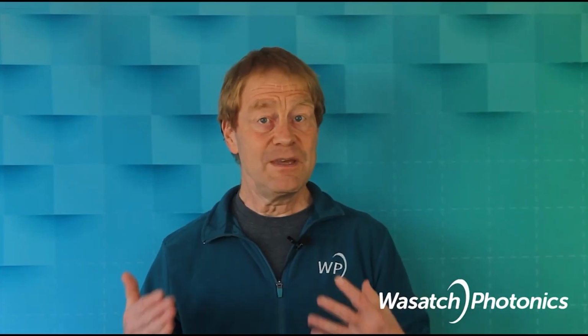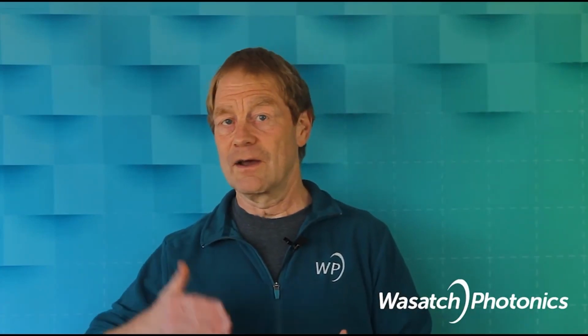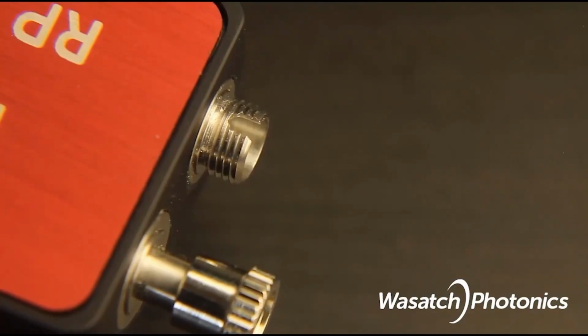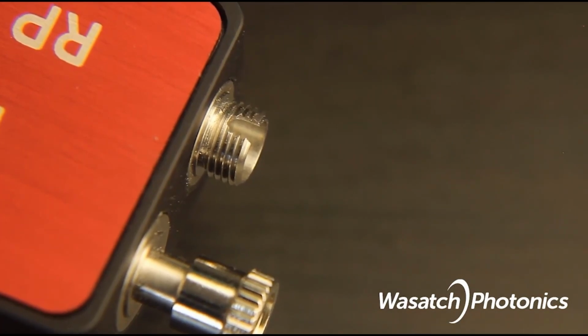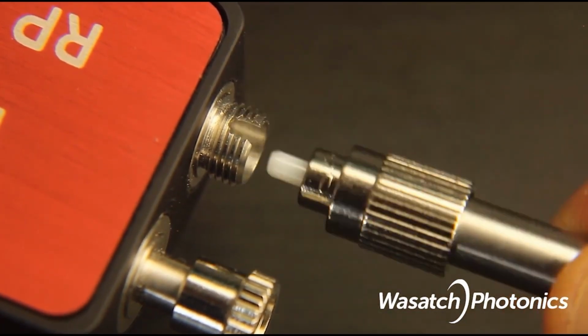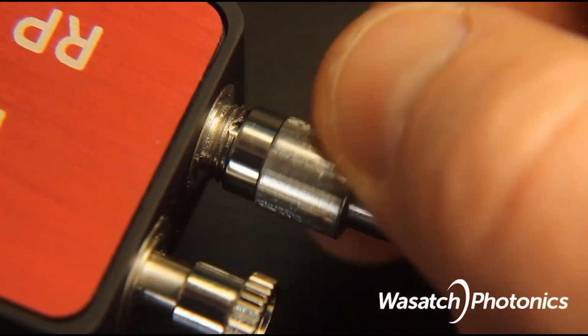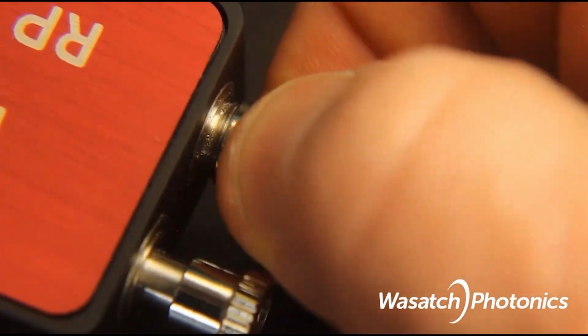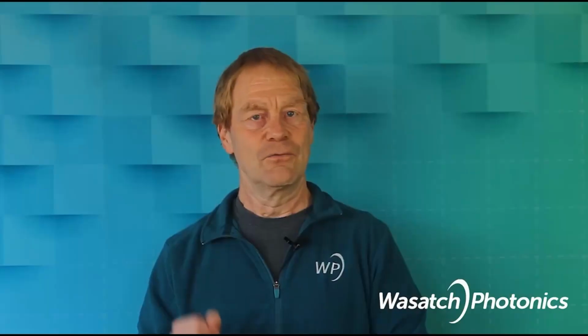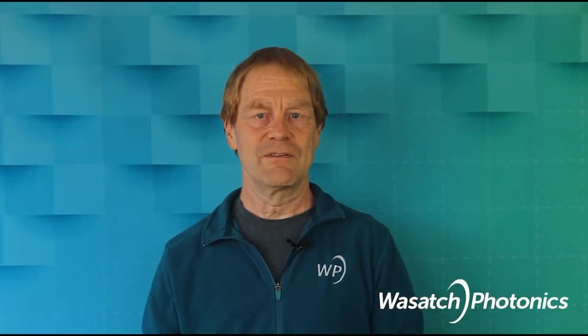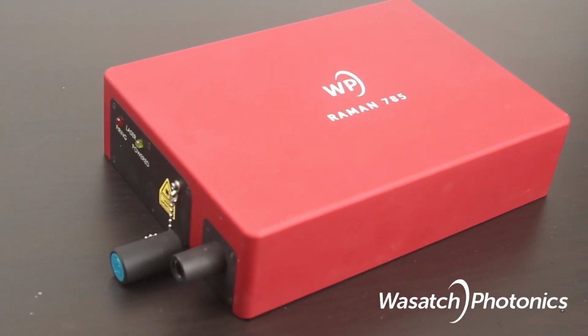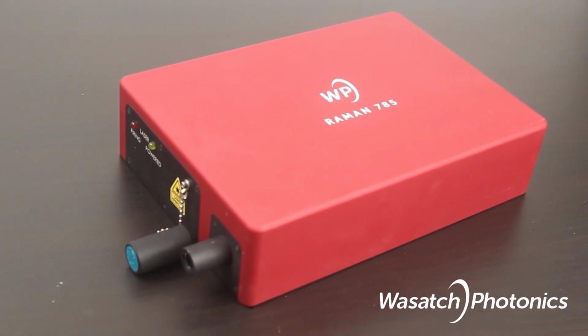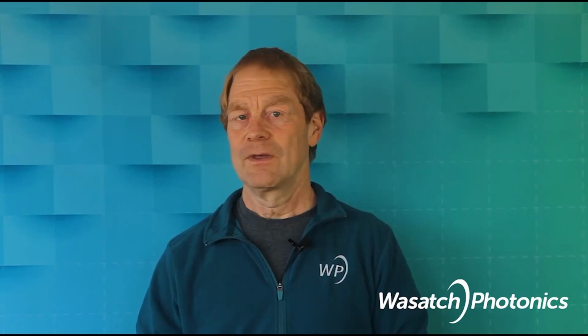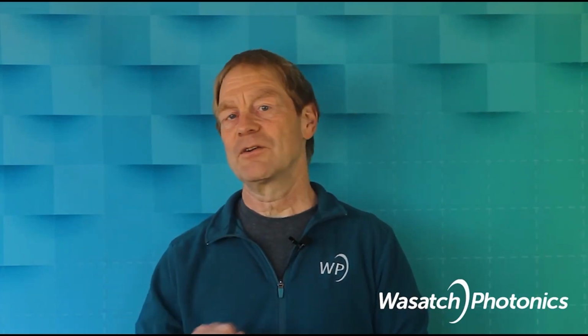The same FC-PC connection you will also find at the Raman probe end. Again, there is a notch on the receptacle and a stub on the FC fiber. As with the laser, orient the fiber the right way, insert and finger tighten. For a fully integrated Wasatch Raman system, the probe is already built into the spectrometer and no fiber connection is needed at all. Next, we connect the spectrometer to the probe.